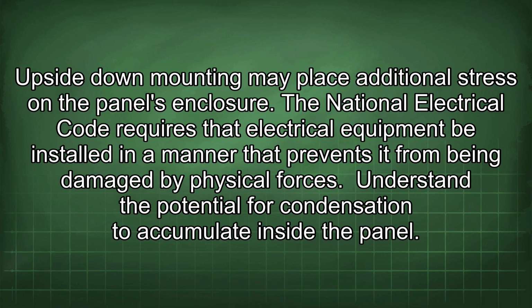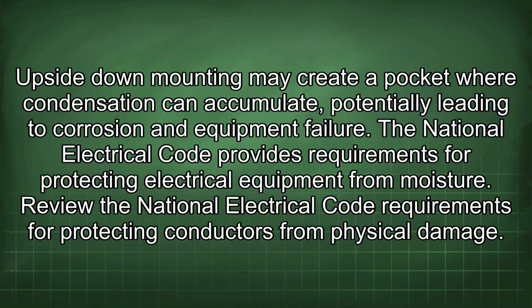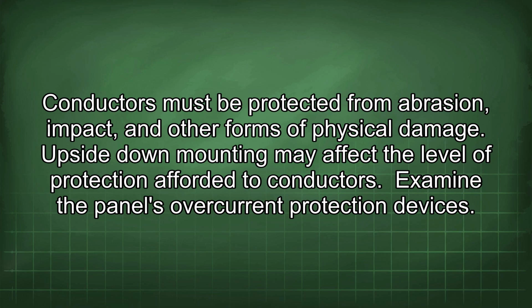Understand the potential for condensation to accumulate inside the panel. Upside-down mounting may create a pocket where condensation can accumulate, potentially leading to corrosion and equipment failure. The National Electrical Code provides requirements for protecting electrical equipment from moisture. Review the National Electrical Code requirements for protecting conductors from physical damage. Conductors must be protected from abrasion, impact, and other forms of physical damage. Upside-down mounting may affect the level of protection afforded to conductors.